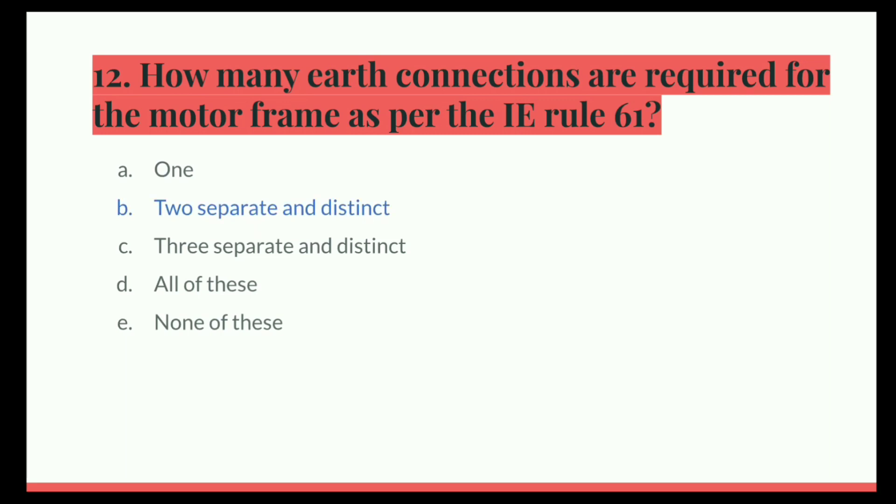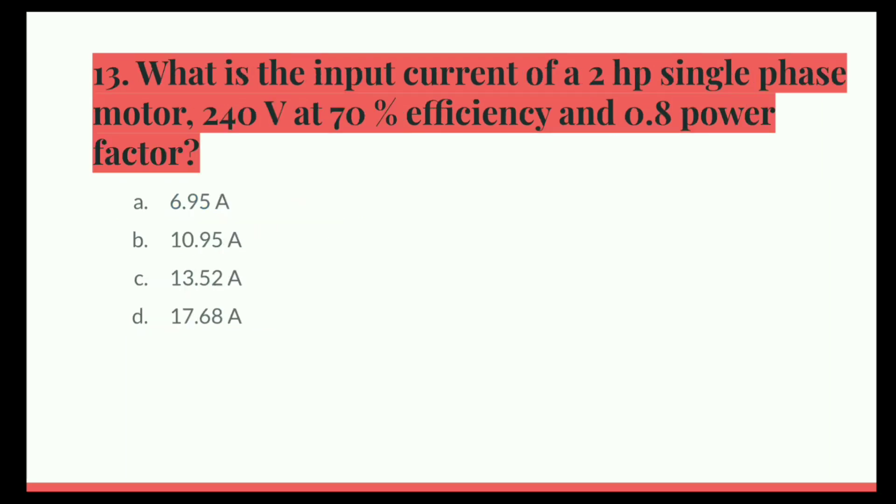Next question. What is the input current of a 2 horsepower single phase motor, 240 volt at 70 percent efficiency and 0.8 power factor? Option A, 6.95 ampere. B, 10.95 ampere. C, 13.52 ampere. D, 17.68 ampere. And the correct answer is 10.95 ampere.